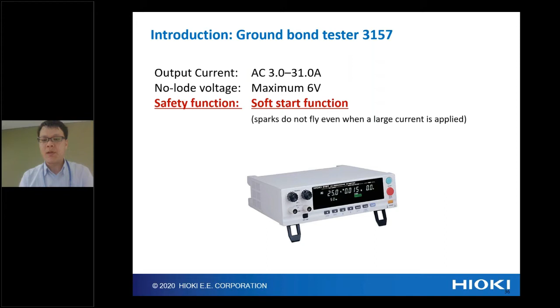So what is the soft start function? This is a diagram of how the soft start function works. The horizontal axis is time, and the vertical axis is output current from the 3157. When the test is ready, we connect the test probe. The 3157 applies a very, very small voltage to check the connection.